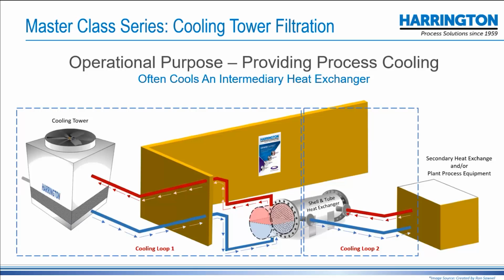So in essence, the cooling tower is a heat exchanger. The shell and tube heat exchanger is a heat exchanger, and it could very well be going to a compressor, evaporator, refrigerant-based system. It's just giving it a leg up on cooling, so energy costs are far less. It's far more efficient. They can also, within the plant, perhaps have a need for hot water. Well, you're producing hot water right there, so they can tap into that as well. So they could use both cool water and hot water from the system.